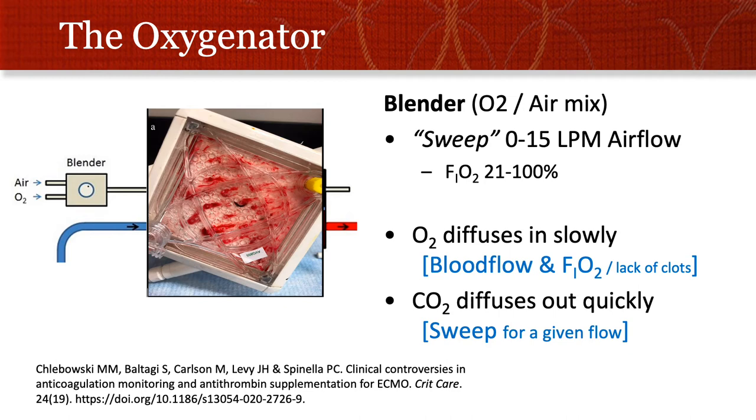This is a picture of a clotting-out membrane on an oxygenator where there are lots of clots all over it — they flushed it through with saline so you can see them. These clots are actually visible, though a lot harder to see when it's filled with blood. They look like little tails or little solid bits within the oxygenator itself.